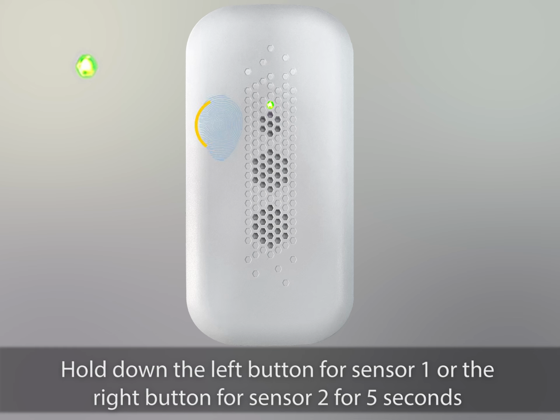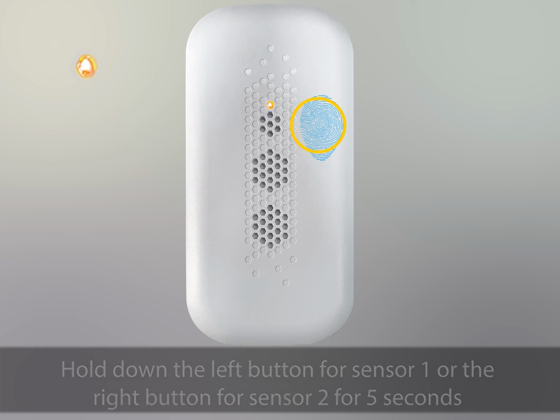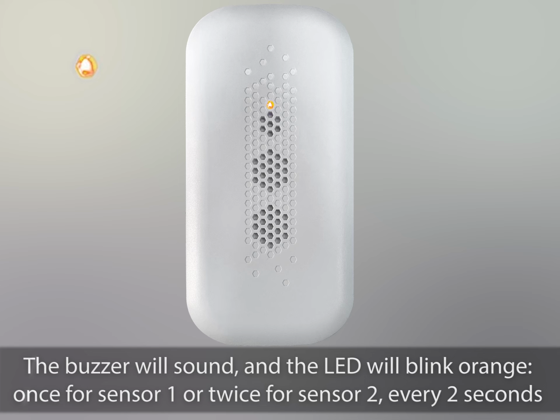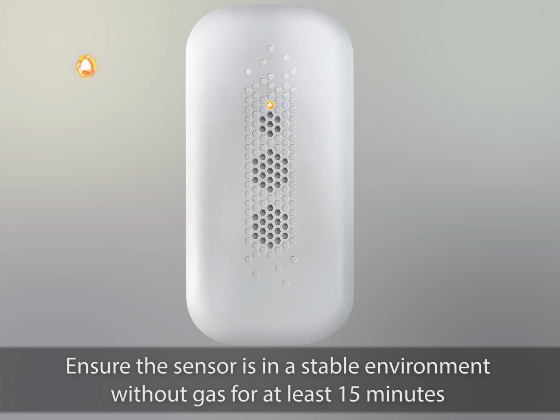Hold down the left capacitive touch zone for sensor 1 or the right zone for sensor 2 for 5 seconds. The buzzer will sound and the LED will blink orange, once for sensor 1 or twice for sensor 2, every 2 seconds. First, we need to apply a baseline calibration.